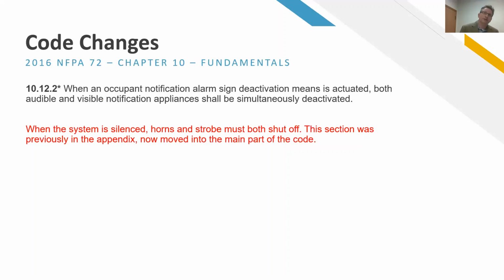Here's a new section regarding the silencing of your fire alarm system. There's a button on your fire alarm system that says silence, and that has traditionally cut the audibles out - whether it's a horn or a pre-recorded voice message, that gets cut out, but the strobes remain active. That's the way it's been for a long time. This is a new section that says if you silence the system, you have to kill both the audible and the visual, because otherwise you're telling the hearing impaired one thing and the visually impaired something else - one group that there's still an alarm, and another group that it's all clear. So this has to be fair for everybody - if we're going to kill one or the other, we have to kill them both.